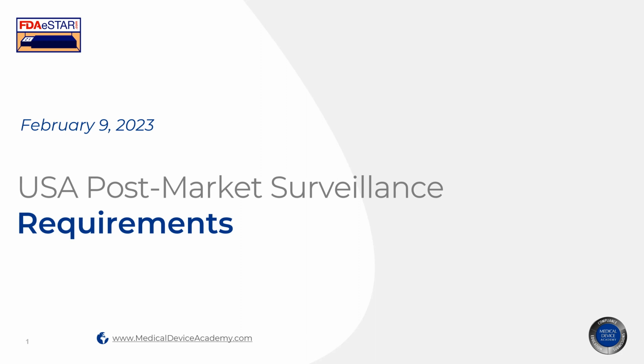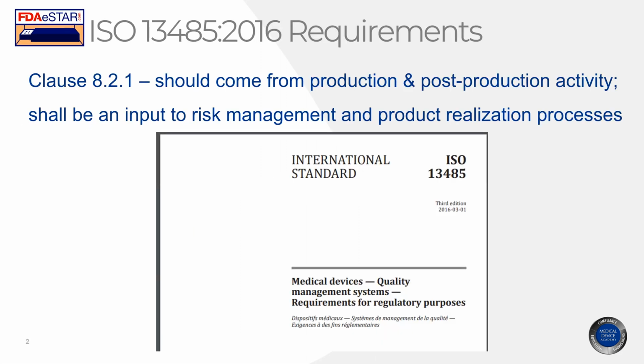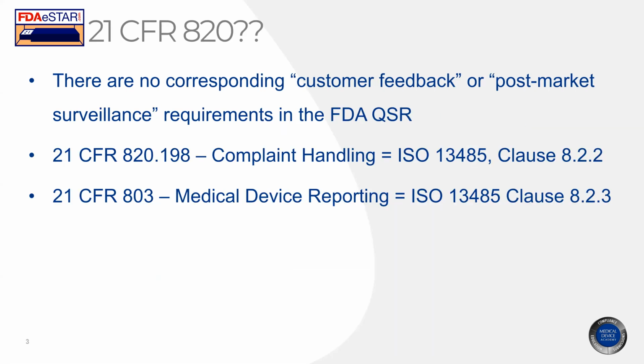So, first slide here for today. What are the requirements for post-market surveillance? You'll find them in ISO 13485:2016. It's clause 8.2.1 for customer feedback. But there is not a corresponding requirement in the QSR. So when you look at the QSR, there's no customer feedback clause or section.